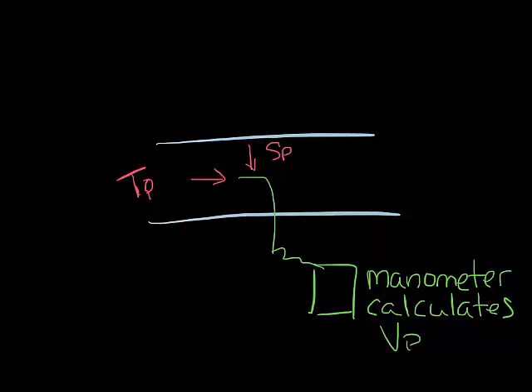Knowing the velocity pressure allows us to calculate the velocity in the ductwork. The equation for velocity is velocity equals 4005 times the square root of velocity pressure.